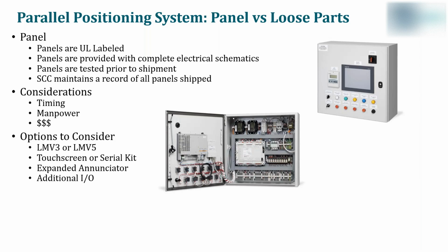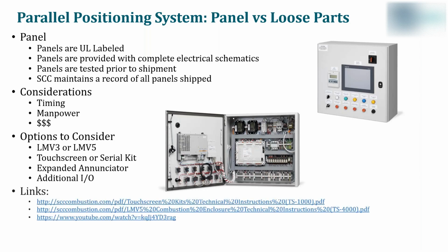Options to consider: LMV5 or LMV3. This will be dependent on the burner size and what features they're looking to have with their control system. Touchscreen or serial kit, expanded annunciator, and finally, additional I/O. This may include additional steam flow, water flow, or additional temperatures that they may want to record.